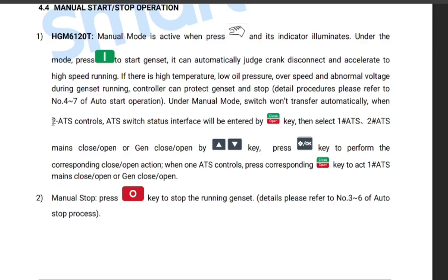Also, as you can see, point number 2, the ATS controller: the ATS switch status interface will be entered by the close open key. Then select A1 and 2. You can manually open and close the ATS contactor from these keys of the controller. Okay, main close open or gen close open by the up and down key. Press the OK key to perform the corresponding close open action. When on the ATS controller, press the corresponding key to act on the ATS main close open or genset close.